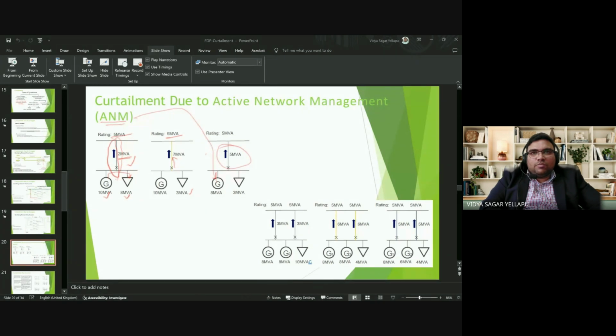In this case, it automatically computes what action the generator should take, and it decides that 8 MVA is the most optimal value of generation from this generator such that this is not overloaded. So it sends a command signal corresponding to 8 MVA, and the generator follows that. Then 3 MVA is the local demand, and the rest of the power, which is excess power, is exported to the upstream network. So this leads to a favorable situation for this asset. That is the concept of active network management. It continuously monitors all the assets in the distribution network and sends command signals to generators or demand side response systems to adjust their usage or generation.